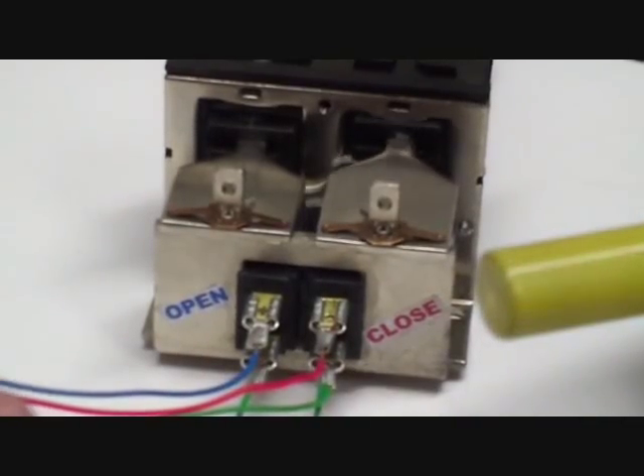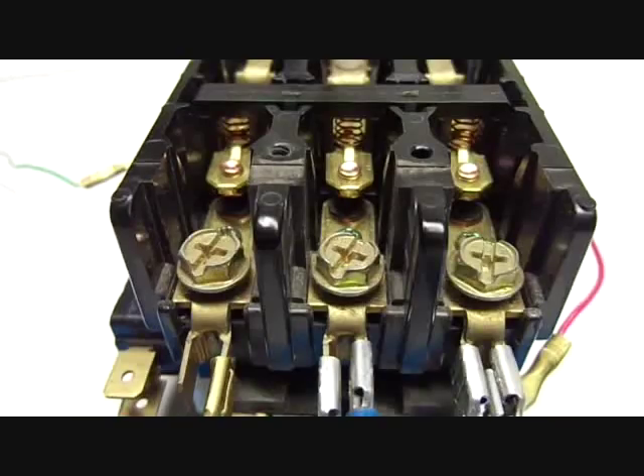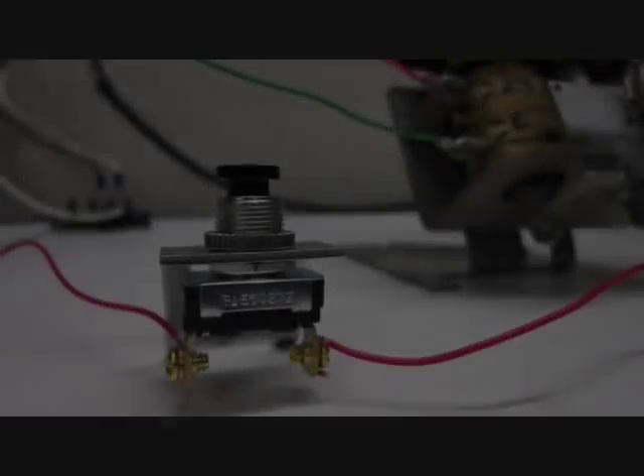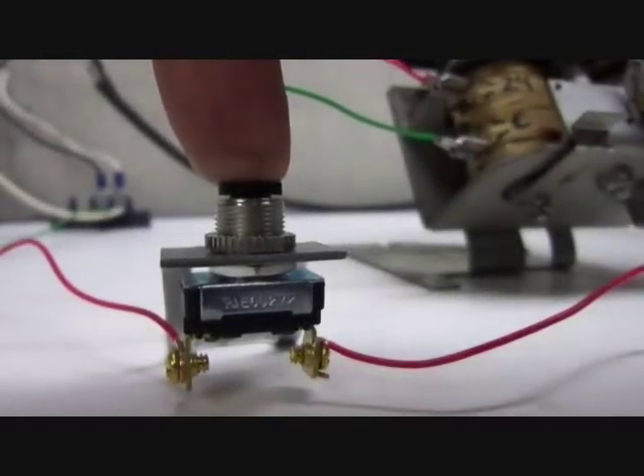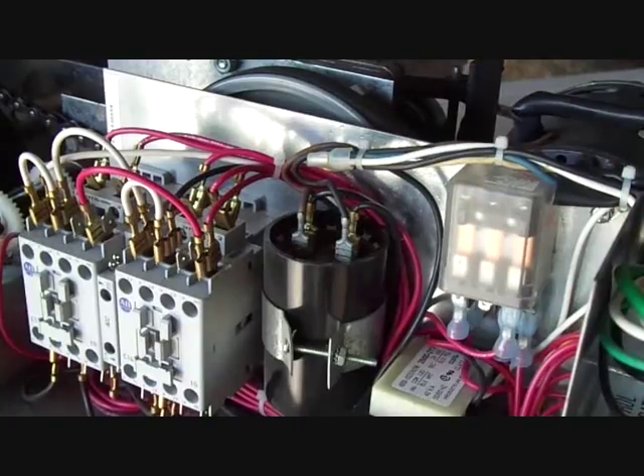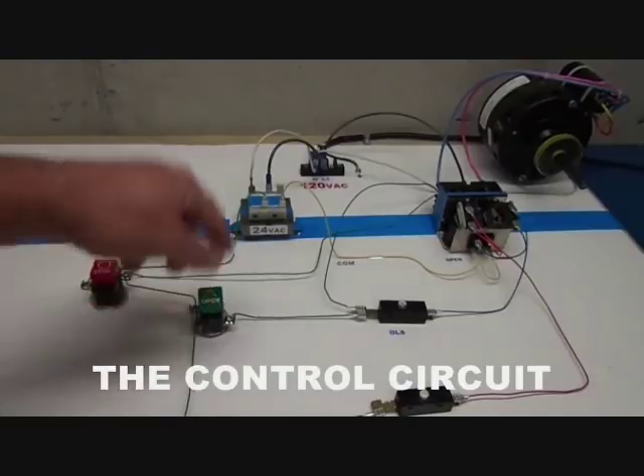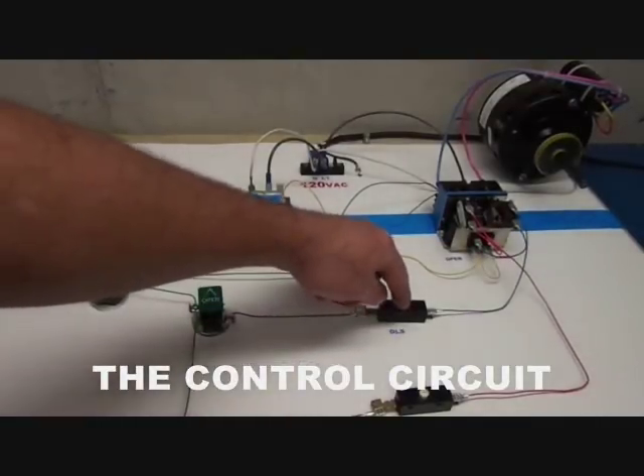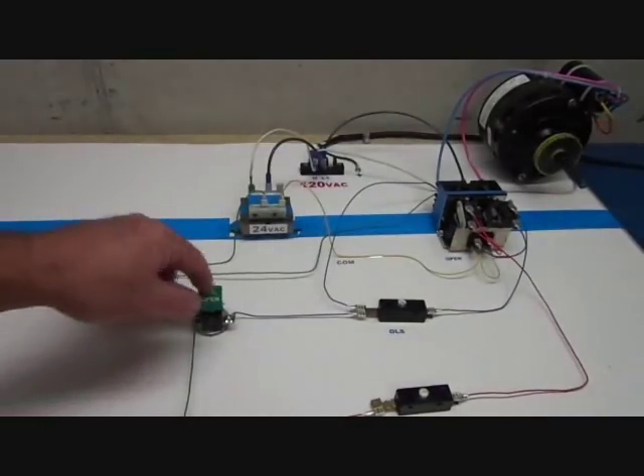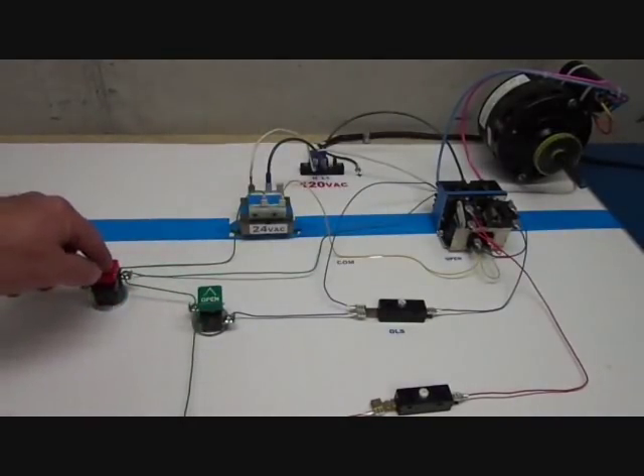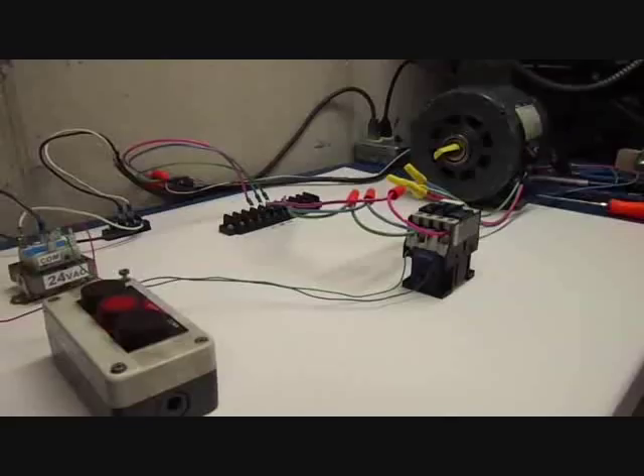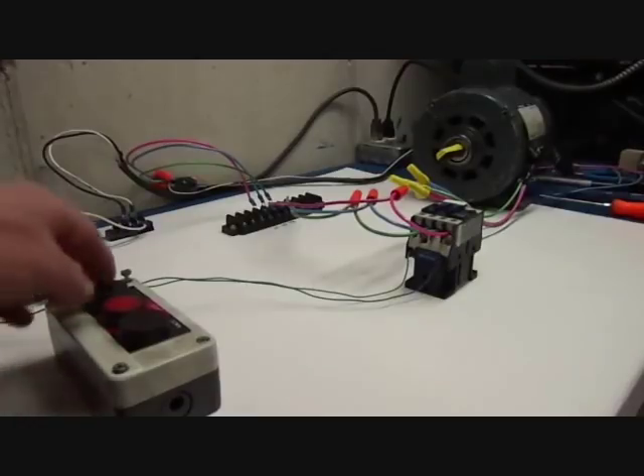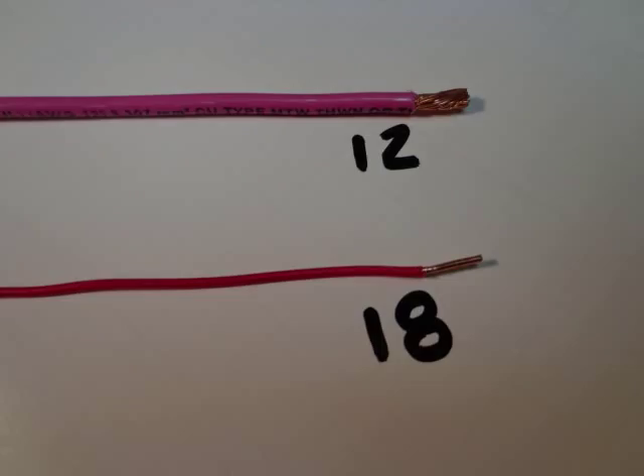So why do we even need a contactor when we could just use a heavy duty three pole switch? There's a lot of reasons. Most of the time, the signal telling the motor to run goes through a bunch of different switches and sensors and stuff, and those components usually aren't rated for the kind of current the motor draws. So it can be a lot more economical and less cumbersome to have a low voltage control circuit with less expensive single pole switches and stuff. The same goes for the wiring. This button might be located 100 feet away from the motor, and 100 feet of 18 gauge copper wire is a lot cheaper than 100 feet of 12 gauge wire.